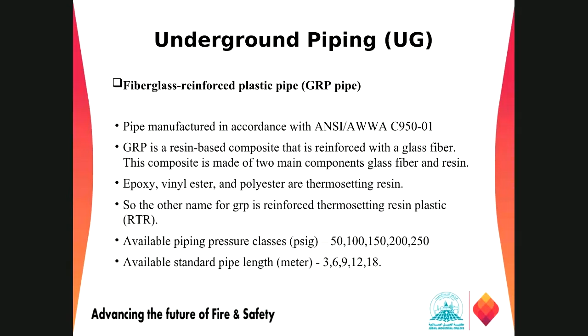So what is the advantage of using the composite application for GRP or FRP piping? If you look at the weight of the piping, it is one quarter of the steel weight. So if your steel weight for 1 meter is around 10 kg, it will be only around 2.5 kg for the FRP or GRP pipe. It also has lower operating and maintenance cost compared to steel, and higher corrosion resistance. Metallic pipe will corrode easily, but this plastic pipe has higher corrosion resistance, and it also has a smooth surface compared to metallic piping, so we have less friction loss.